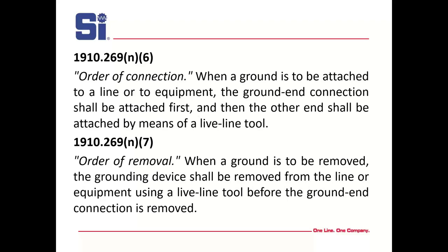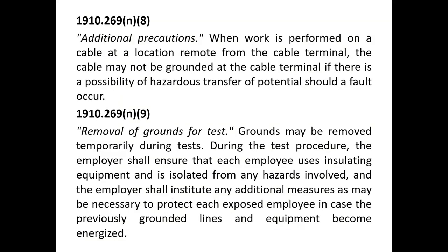The next two rules are very simple: connect the ground connection first to the ground, then attach each phase. When you take it off, you take off each phase, and the last one you take off is your ground connection. If work is performed on a cable location remote from the cable terminal, the cable may not be grounded at the cable terminal, if there's a possibility of hazardous transferred potential. In other words, they want you to ground the other end to ground the whole cable.